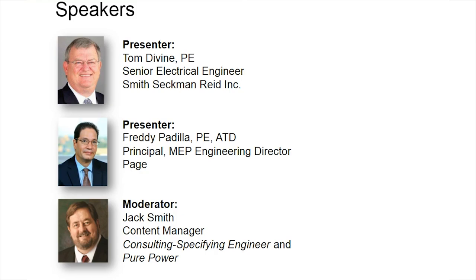So the way that I typically meet that requirement, and we've been doing it for a long time, is to install an outdoor disconnect switch, maybe fused, usually Kirk key interlocked or somehow mechanically interlocked with the generator breaker, and use that as a place to attach a temporary roll-up generator, a rental unit that might be on the back of a truck. We also use that for load bank testing at the same time.